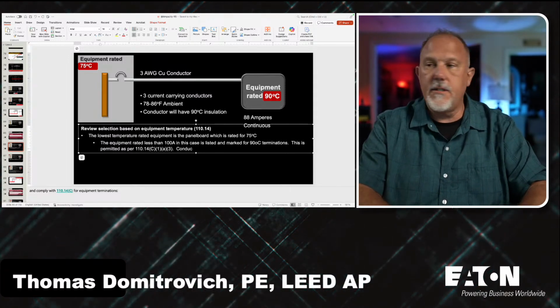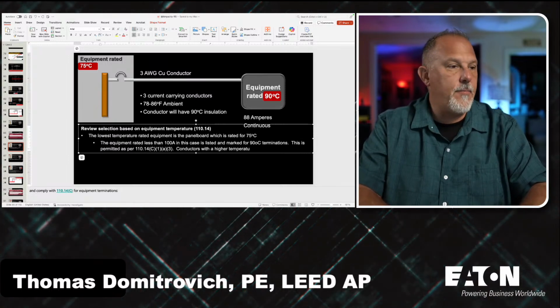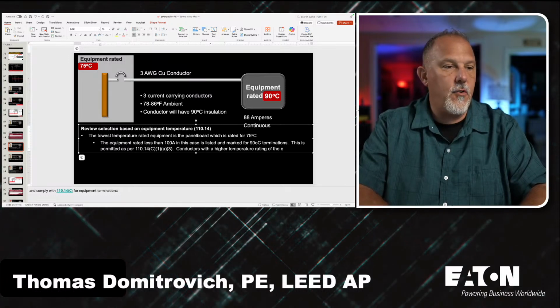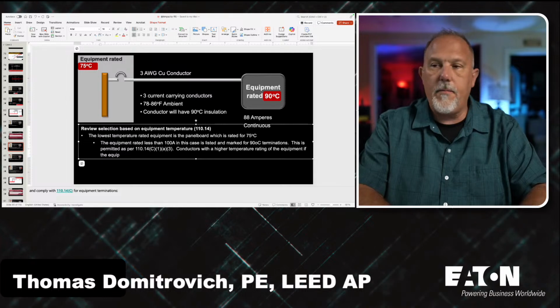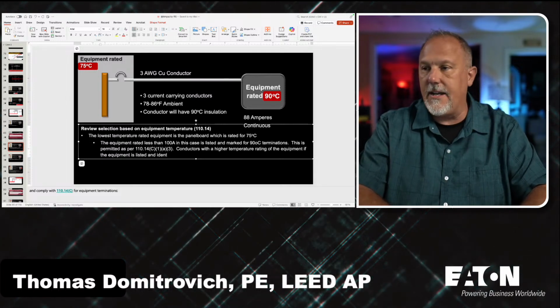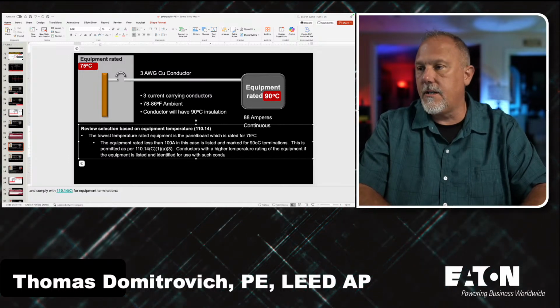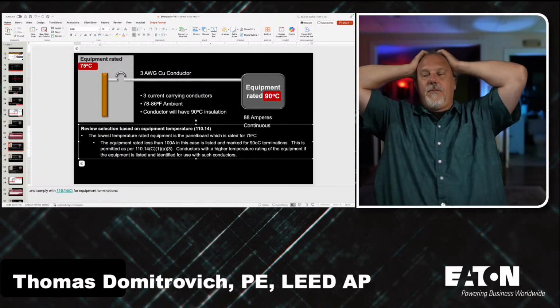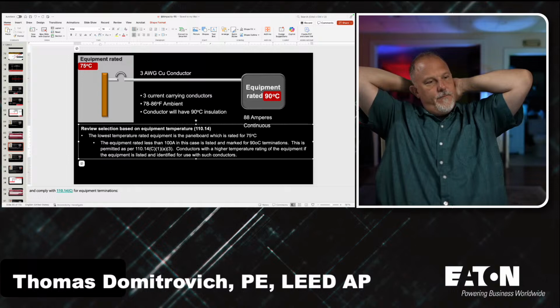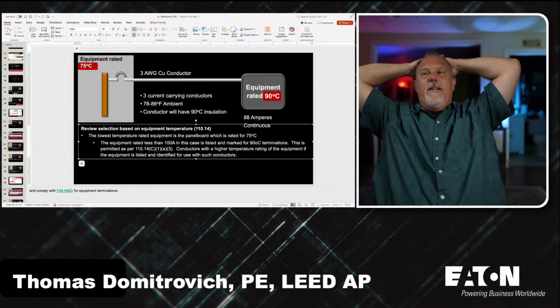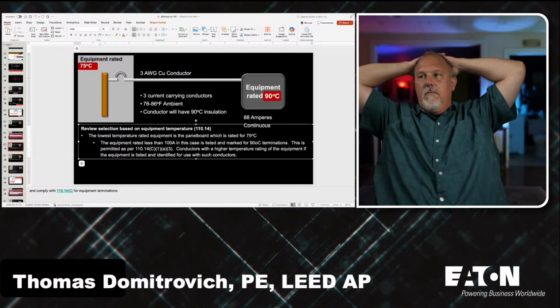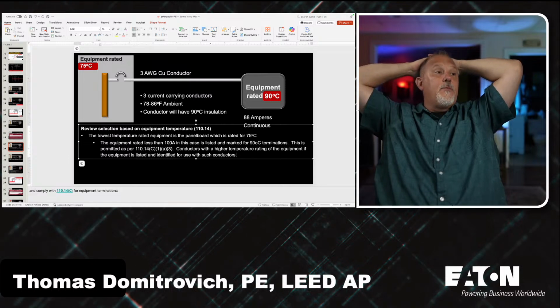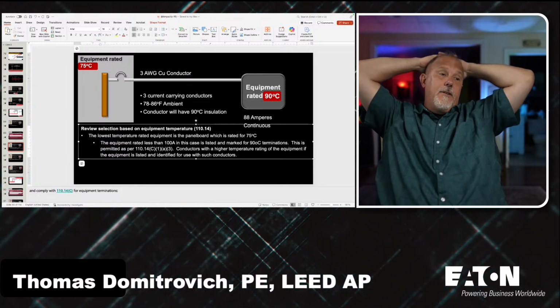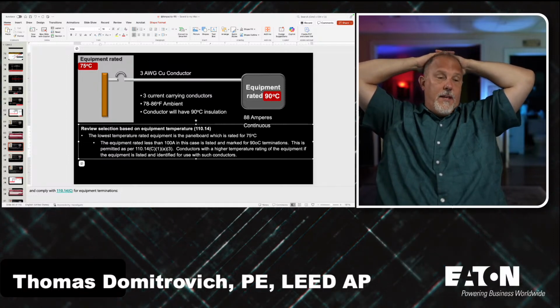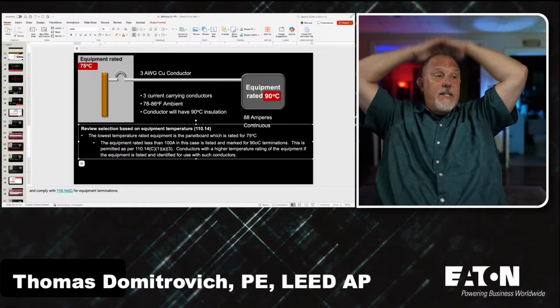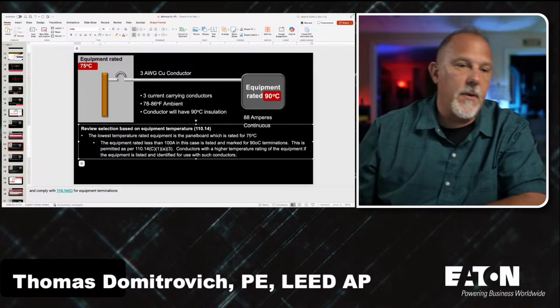Okay, conductors with a higher temperature rating of the equipment, if the equipment is listed and identified for use with such conductors. Does that fall under it, Dawn? Think about this. If my equipment is rated for 90 degrees C, it's rated for 90 degrees C. My conductor doesn't have a higher temperature rating than what the equipment is listed for, because the equipment is listed for 90 degrees. So I'm having a little heartburn.